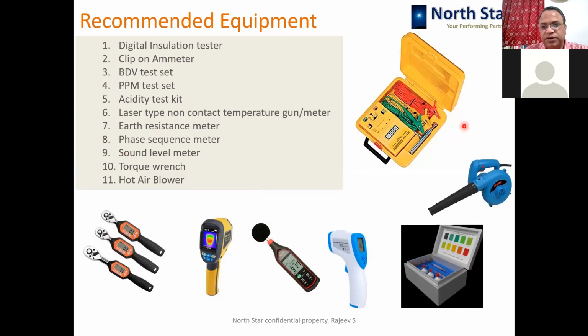Then the earth resistance meter. This is the earth resistance meter, which is again not a very costly piece of equipment, but very useful. A phase sequence meter has to be there. A sound level meter, especially when you are having transformers, it is a good idea to have a sound level meter. Torque wrenches, hot air blower, and the thermal scanner. It is optional because it is a costly device, but if you can, you should have it. So this is about the recommended equipment in a laboratory.